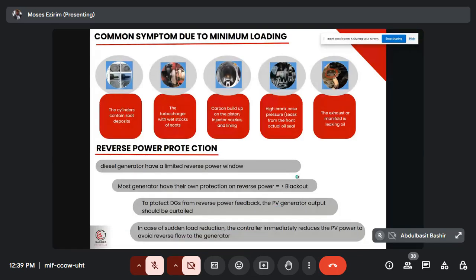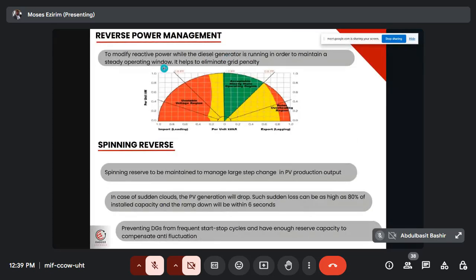The controller can also modify the reactive power the generator is running with, in order to maintain a steady operating window. All right, so I'm sure you know that in some countries, there is a certain power factor that you should maintain. If you go below that power factor, you pay some fine. When the power factor reduces, the current increases, and once the current increases, you pay more money. All right, so the controller helps to minimize that.